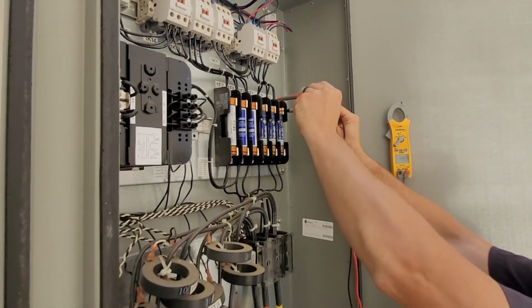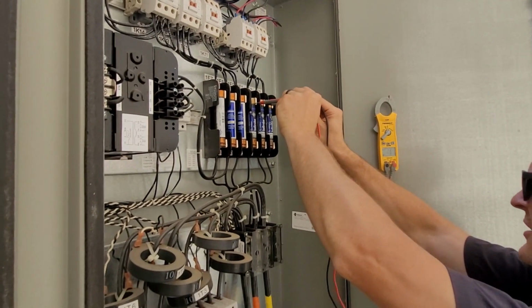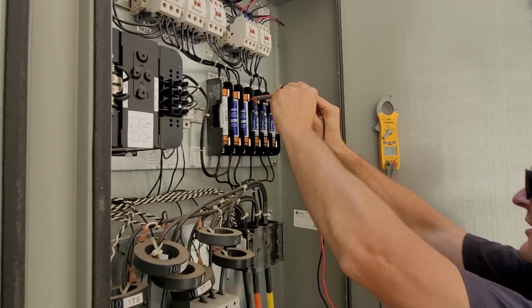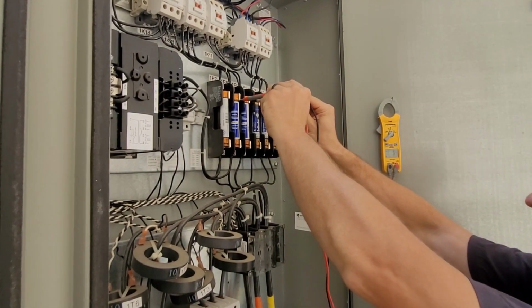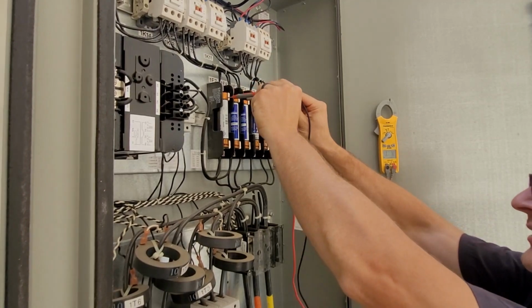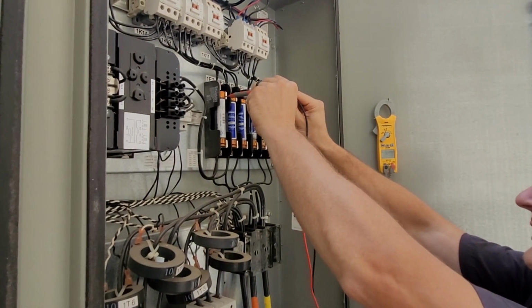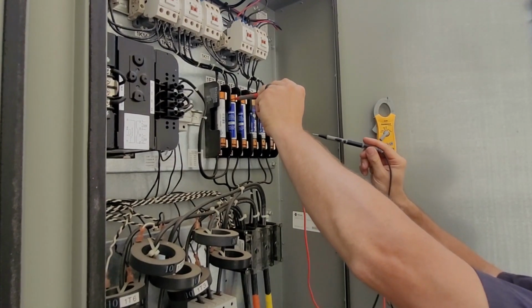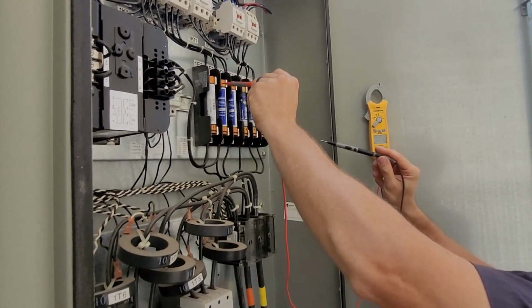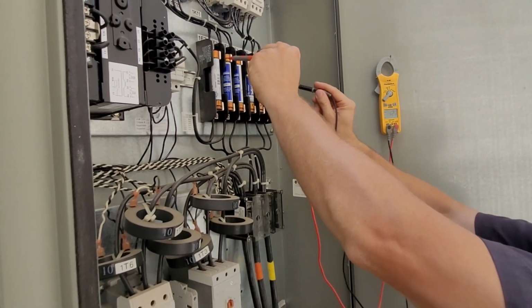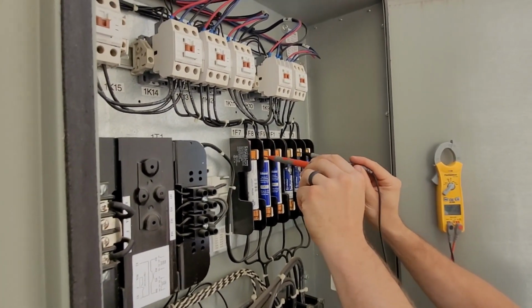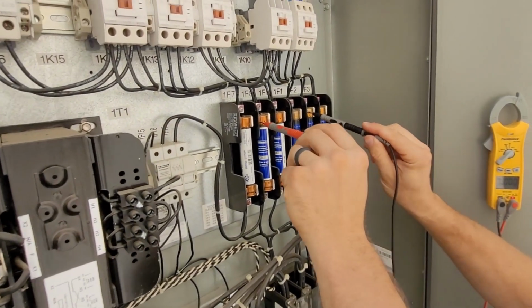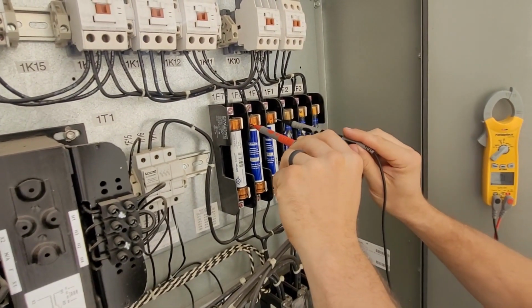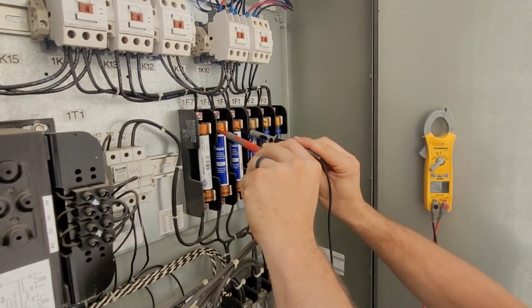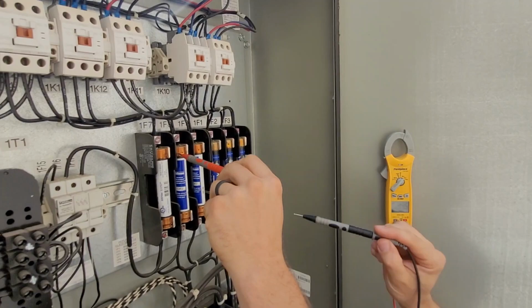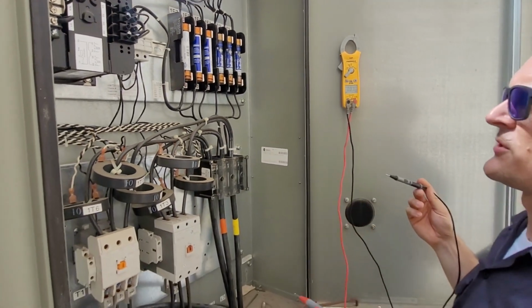Check between 2 legs. 480 there, 480 there, 480 there, 480 there, 480 there. Now, if you catch one, the reason you want to try it several different ways is because you might catch one that's on the same leg, like this one and this one. They read 0 when you go between them, and that might lead you to believe that there would be something wrong with those fuses, but it's not. You just need to check it with a different one. So now I got 480. Check it to ground, check the legs between each other, and just think about what you're doing.